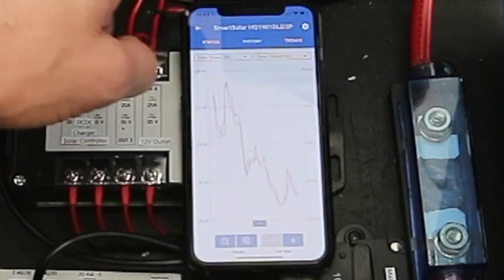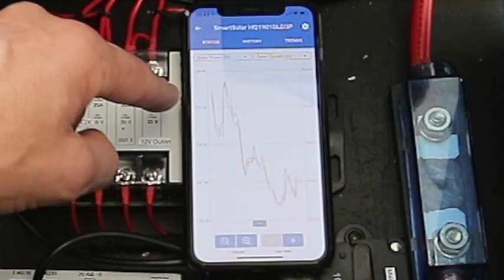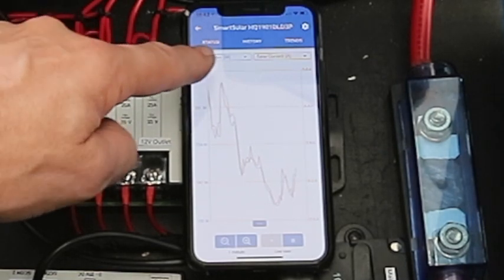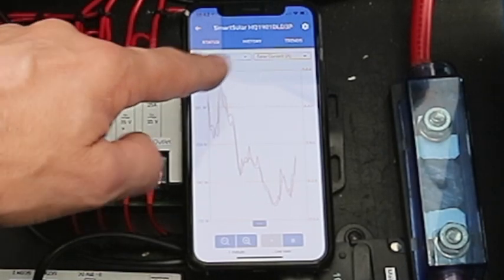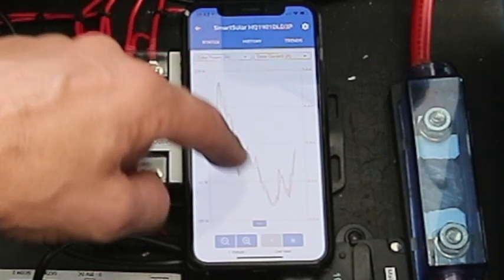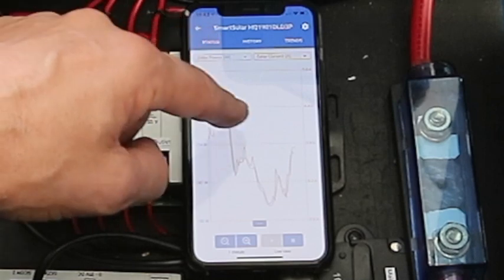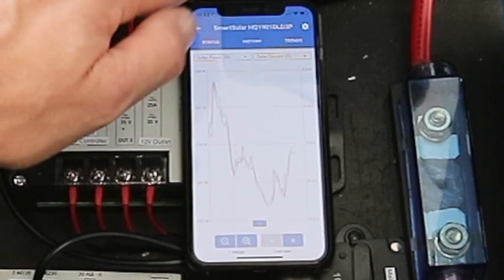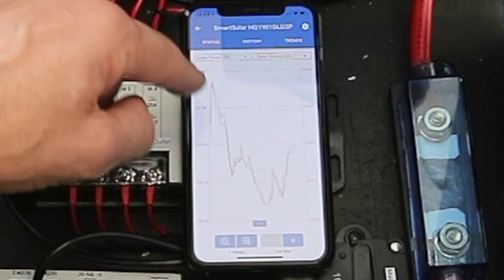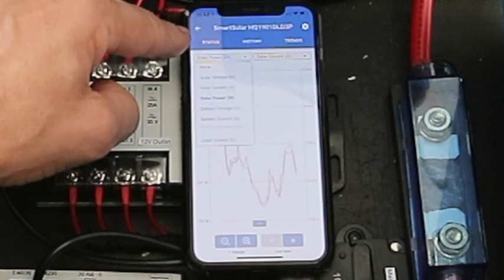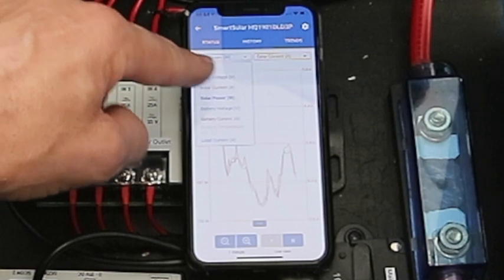And then for commissioning, this trend is just great. So this is showing solar power in watts and solar current. And typically when we're commissioning, we cover up panel at a time.